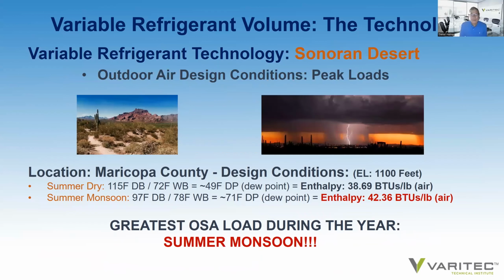Well, in Arizona, this is an interesting phenomenon, because we have to be aware in Arizona when our peak summer design days are. I remember my earlier years in the industry, I used to think it was in June when it was 115, maybe even 120 we've seen more recently. However, our greatest load in Arizona, in Phoenix, Arizona, and in the Sonoran Desert, is during our monsoon season. If you look at the total energy, if you look at the sensible heat energy in the air plus the amount of water vapor in the air or humidity, the total load of a summer monsoon day is actually greater than a summer design condition within June at 115 degrees.